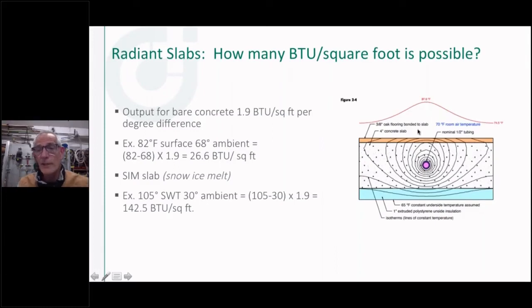If you're limited by that surface temperature, that's going to limit how much heat I can get out of a square foot of a concrete slab. So let's use an 82 degree surface temperature, and let's say the ambient temperature in that building is 68 degrees. 82 minus 68, the factor is 1.9 for a bare concrete slab without any finish on it. I'm going to get about 26 BTUs per square foot. So when you hear people say the most I can get out of a concrete slab is 28 or 30 BTUs per square foot, that's where that number is coming from.